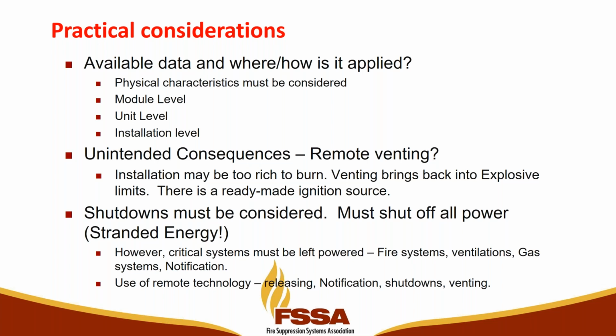Have radiant energy sensing detectors been evaluated in order to initiate activation of the fire suppression system? It is happening. There are some tests going on. There's a number of sensors that have been deployed for some of the big testing agencies to see if we can get data. It is still very sketchy, but I think that's a very good option when we come to detection. If you can read down the hot aisles, I think that's a very good option.